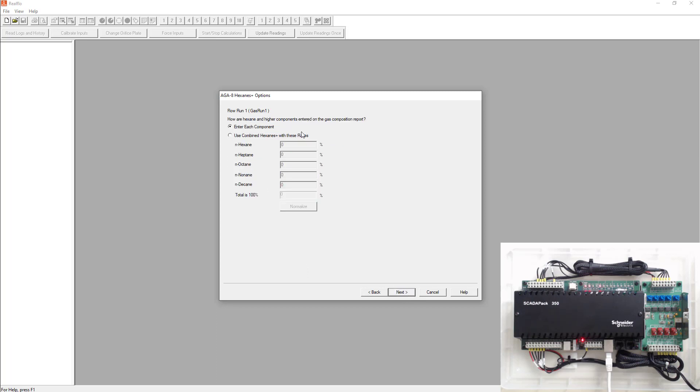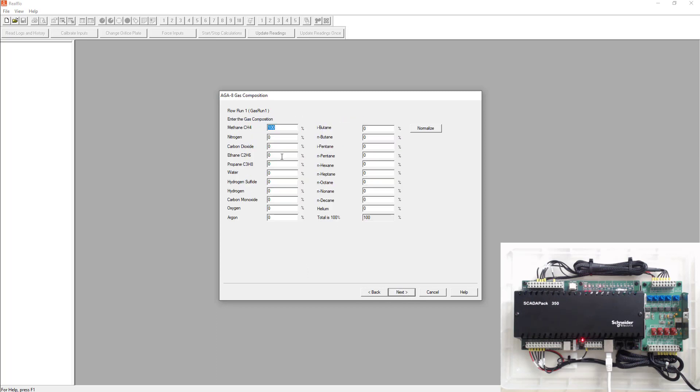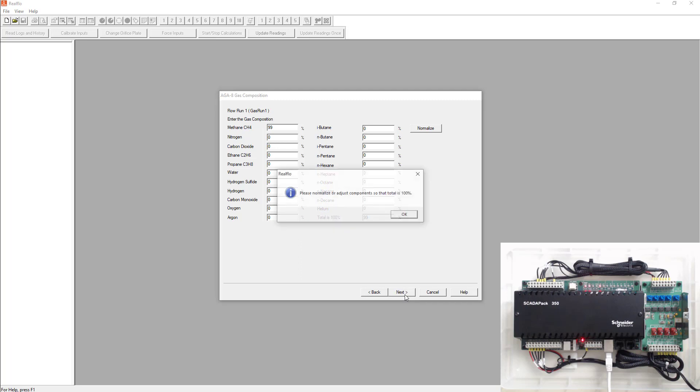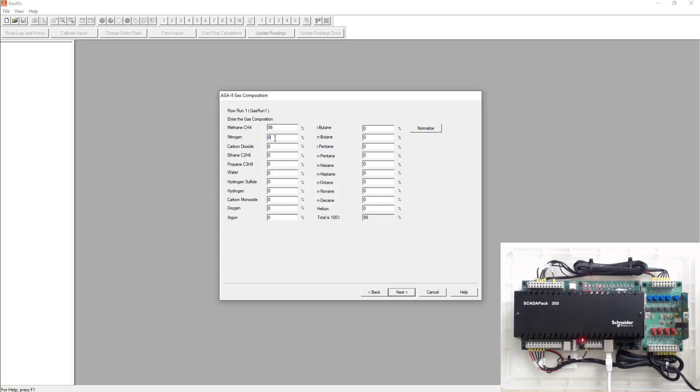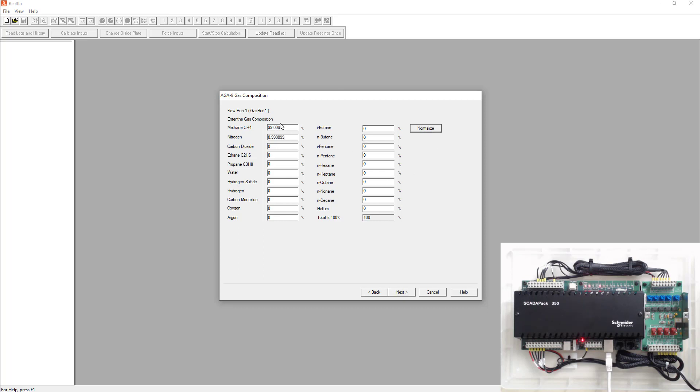We're going to enter each component here. So just select next. Again, you could go ahead and put in your gas composition. So if you put something in that doesn't total a hundred and try to go next, it's going to obviously tell you that you have an issue. If you get your gas component back from the lab and it's off by a fraction of a decimal, you could hit this normalize and round it for you as well. So we'll just go next.